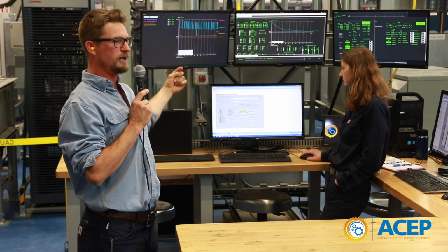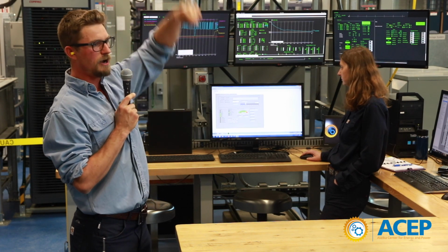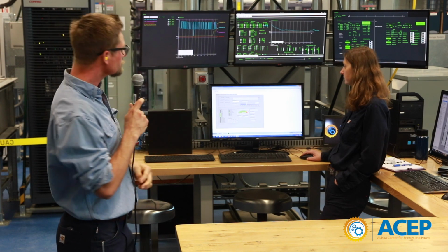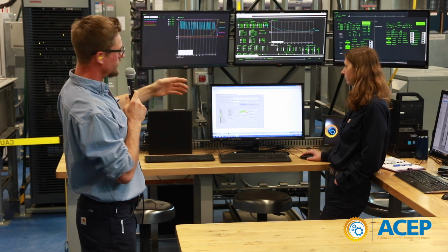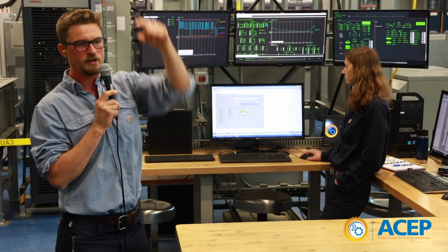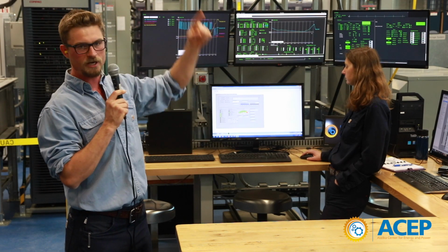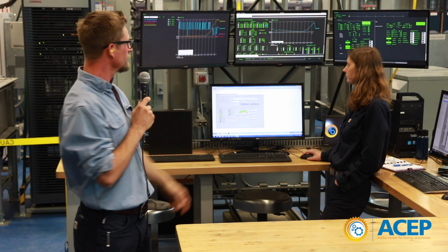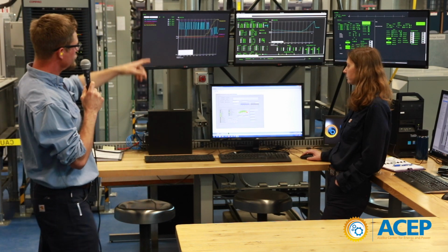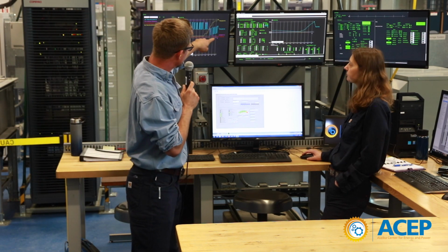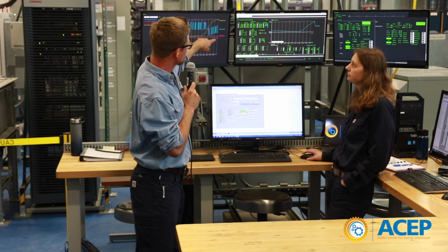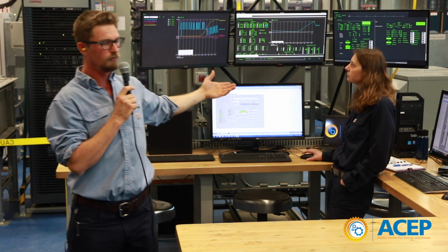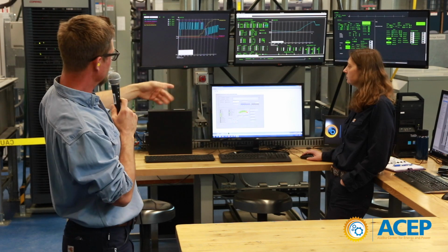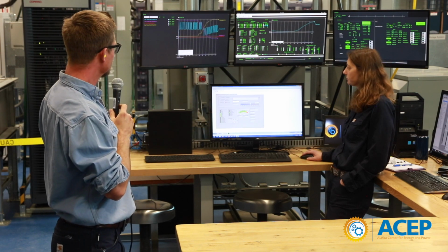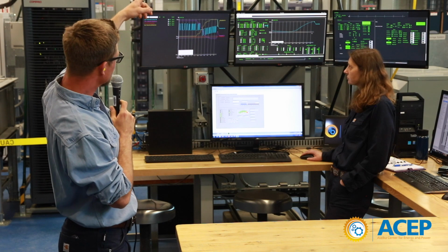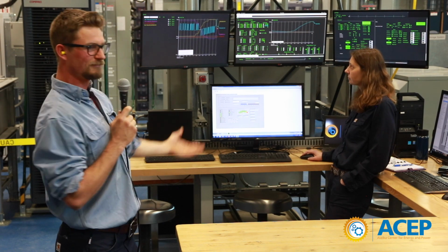It can take power in and put power out, so we can let the wind power go higher than the load. The inverter will just go positive power output or negative power output, balancing out whatever's happening between the wind power and the load. If we increase the wind, look — our inverter goes negative power, so it's charging, because we have more wind power than load. And if the wind power drops down, it goes positive again. Pretty cool.